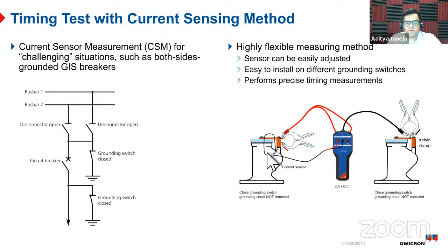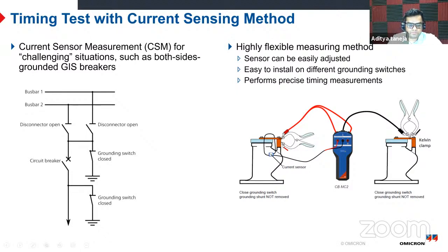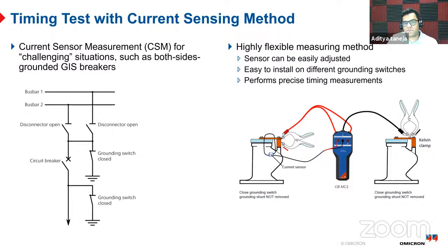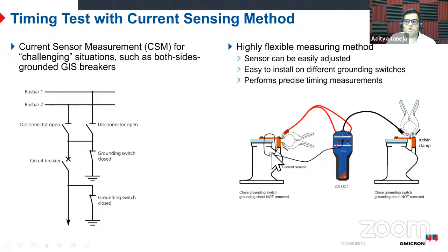So we check that change of current, and that gives us an indication that the breaker is operating. And this is a very sensitive measurement because we are measuring a change of a few tens of amperes, and it is happening while the arcing contact resistance is also there. So the signal which we get from these current sensing loops can also be used for analyzing the arcing contact length if we do it with the travel measurement. So a lot of analysis can be done without opening any ground, and this is good because in a GIS, opening a ground is a big topic, needs a lot of clearances.